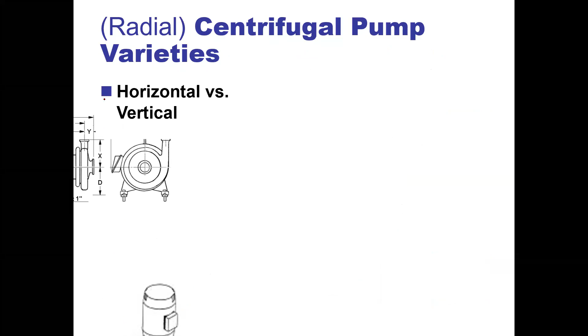Now, this is not so easy to tell which side is suction and discharge, right? We don't have a suction and discharge so easily shown. But what we can look for is our context clues. We can see that over here, this dives down and goes into the center, so that must be our suction. But even if we can't see that, another thing we can see is that the volute increases over here - it's increasing in that area, so that must be this side part of our volute, so that's going to be our discharge.